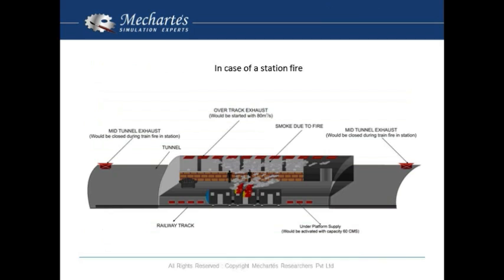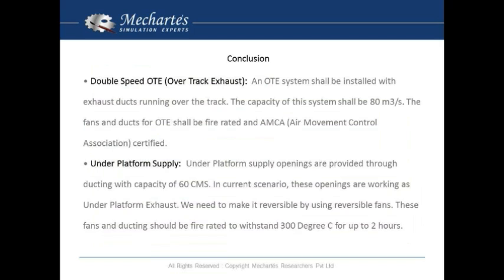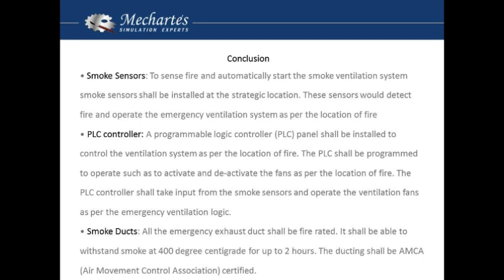This was the finalized emergency ventilation system designed using FDS and CFD simulations. In case of a station fire, the under-platform exhaust is reversed to supply air, and overtrack exhaust of the required capacity is installed. In case of a tunnel fire, the mid-tunnel exhaust provides the required ventilation. The components installed in the retrofit job include overtrack exhaust, under-platform supply with a reversible fan with AMCA certification, smoke sensors, PLC controller, and smoke ducts.